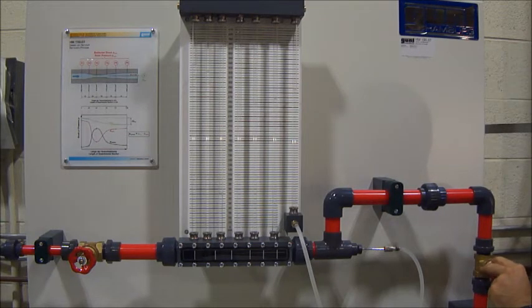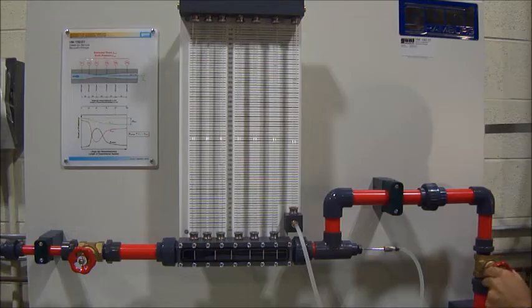Then record the static pressure and total pressure for each of the six locations as done prior and re-measure the flow rate.